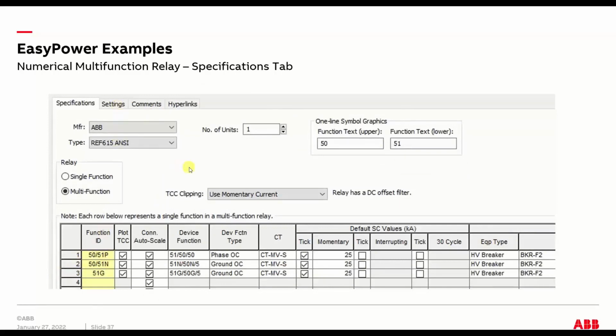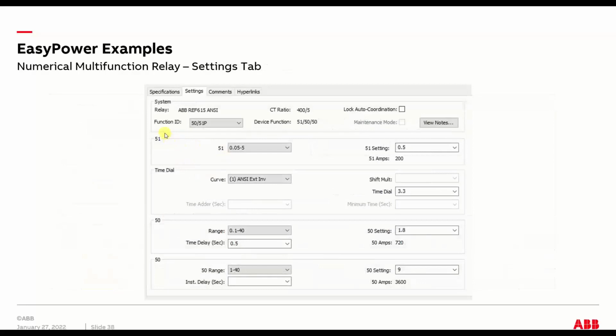And then under the settings tab, this is for device number 1, is your 50/51P. That's why it's called it. So you can call it whatever you want. Then you have your 51 protection. This is the range, which for this case is preset. And then you have your setting, and that's the tap value. And here's your time dial. This is where you pick the curve.